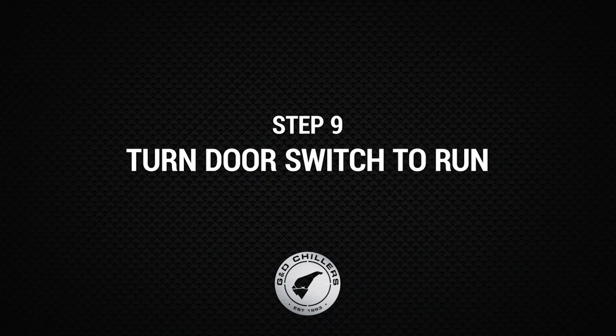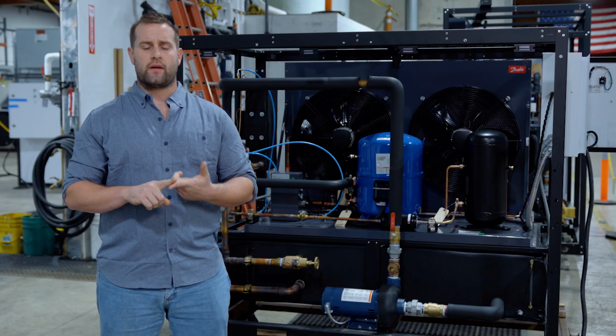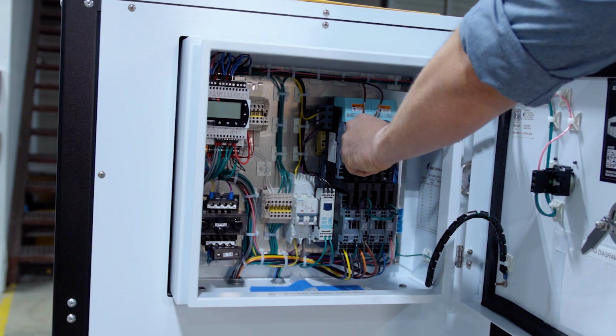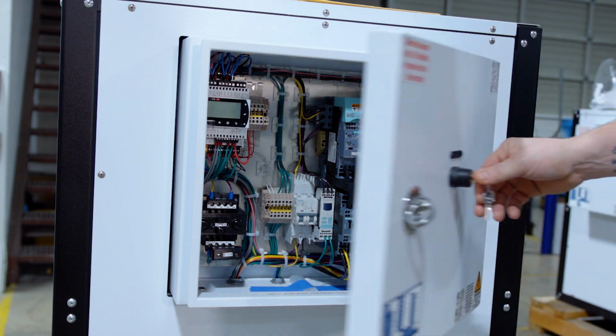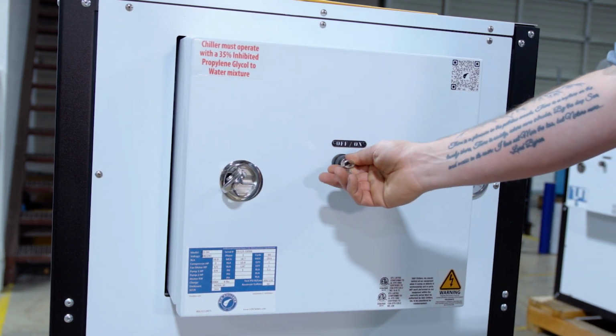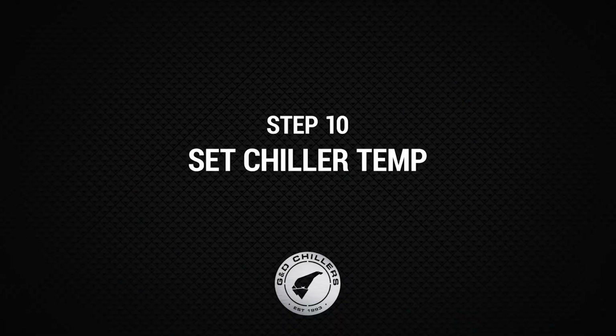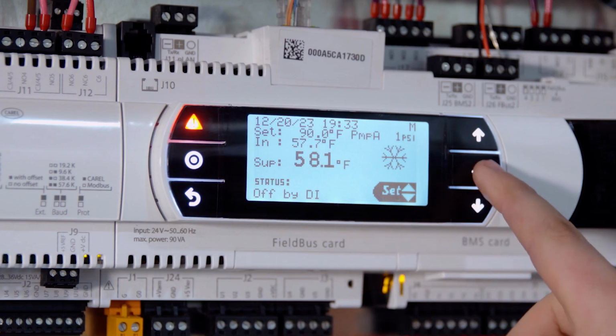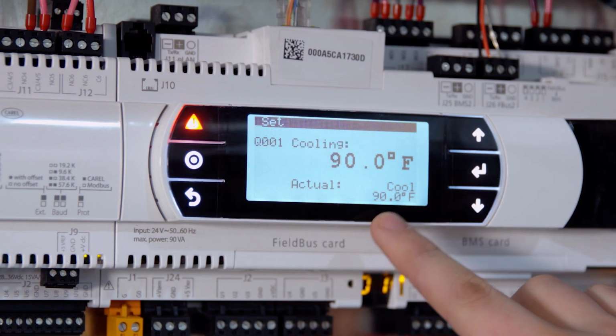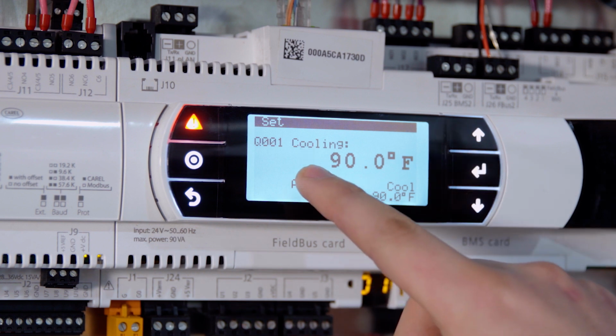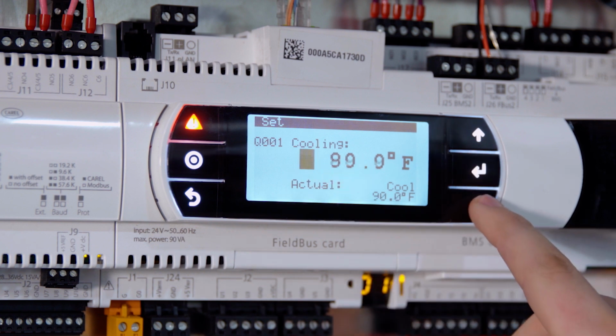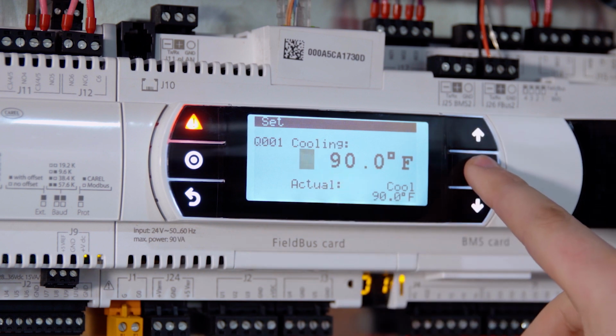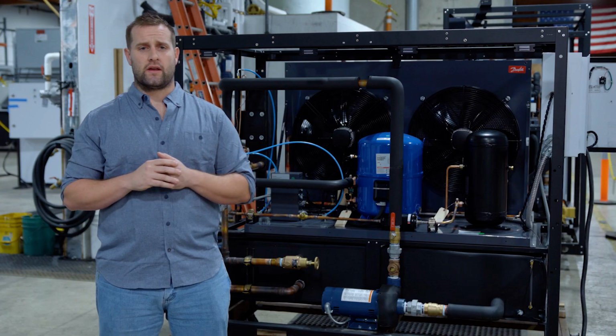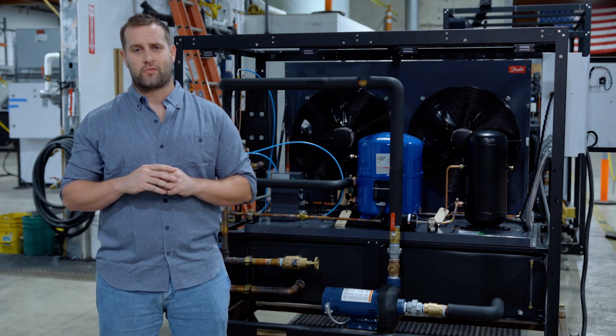The next step on our startup, once you have your oil levels verified, once you have the valves open, and the glycol mixture correct, is to simply turn on the unit. From there, you're going to take the door switch to run, and you're going to navigate through the controller to set your set point for your process. If you have any questions about navigating through the controller, we'll have videos on our website, and you can call into tech support. Thank you.